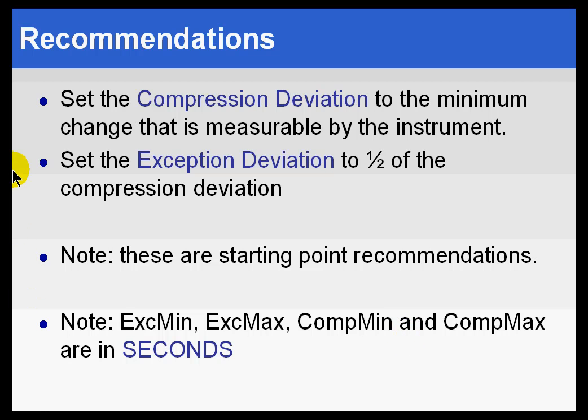Now, finally, we get to the point at which we're ready to make some recommendations as to what you set for the compression and exception deviation. In general, for the compression deviation, we suggest you set it to the minimum change that's measurable by the instrument and then simply set the exception deviation to half of that compression deviation. Over the years, that seems to give people satisfactory results.